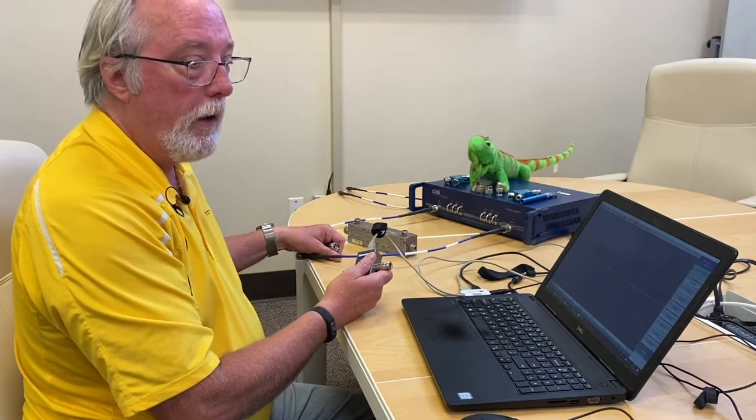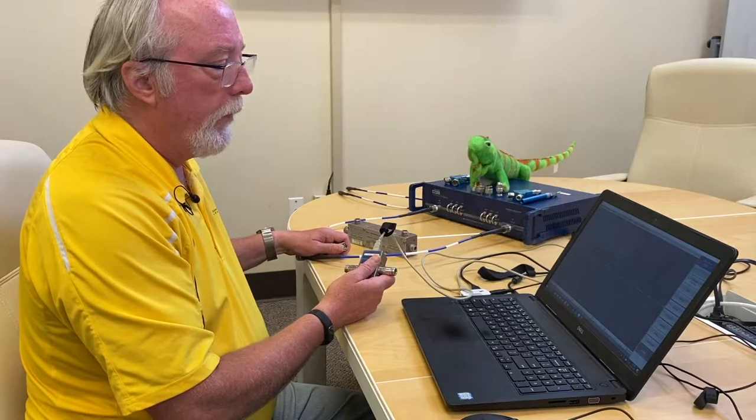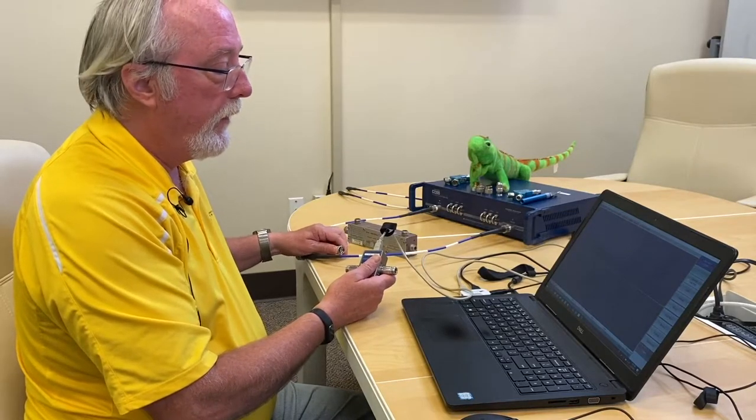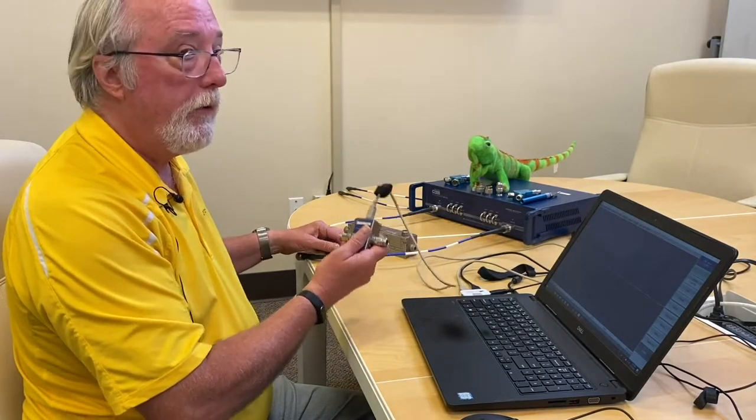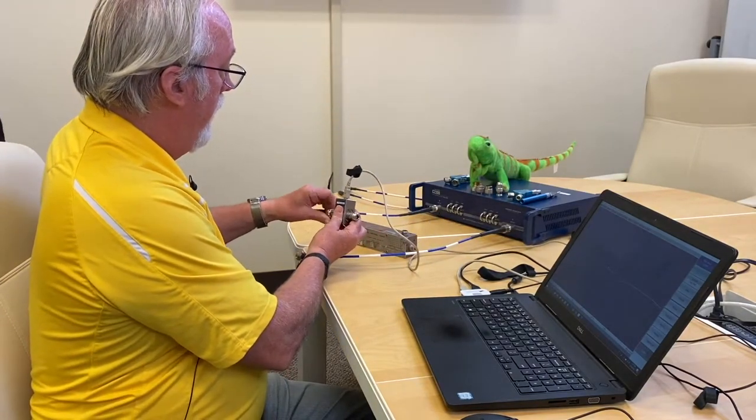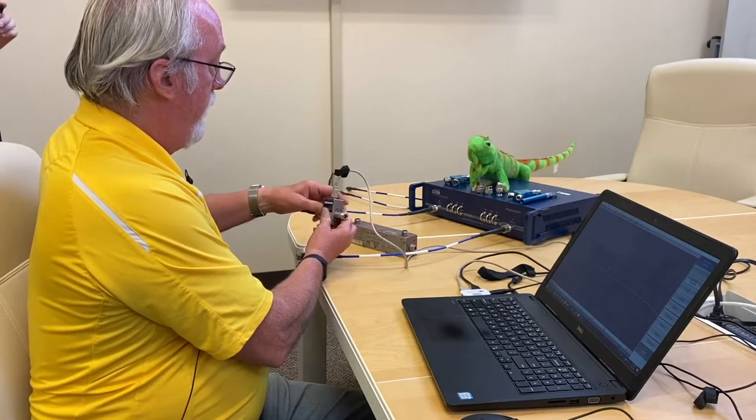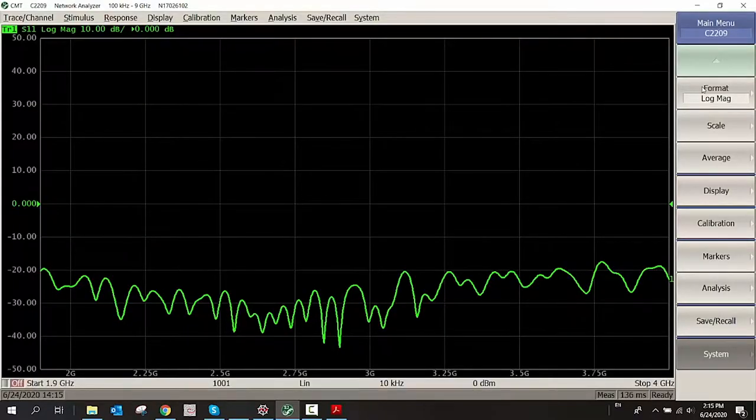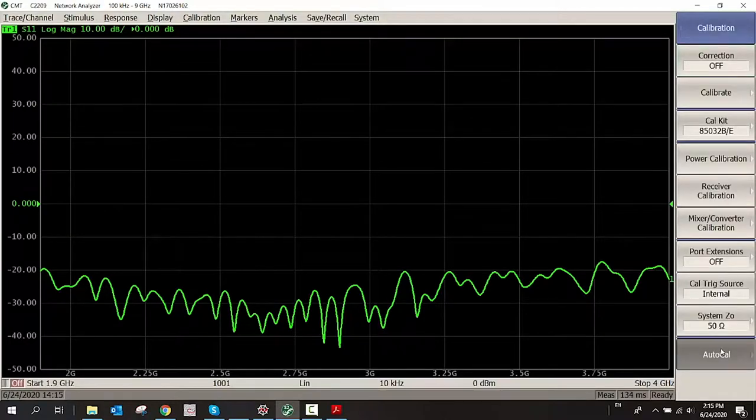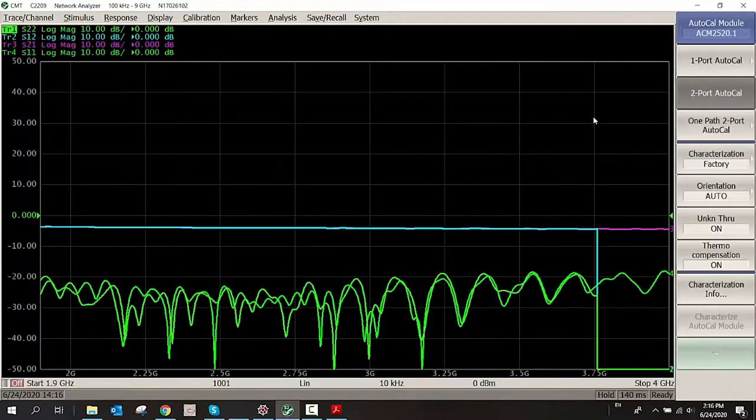Then I'm going to use this automatic calibration module to calibrate the VNA. And I'm using this for two reasons. One, it's very fast. And two, it gives a superior calibration compared to any other method. If you used a SOLT calibration kit, the results you get from the VNA will not be as good as you get with an automatic calibration module. So I'll attach it and do my calibration. Auto-Cal, two-port Cal. And it's done.